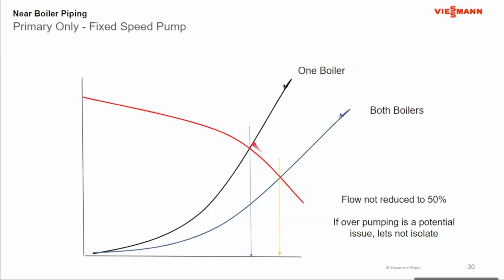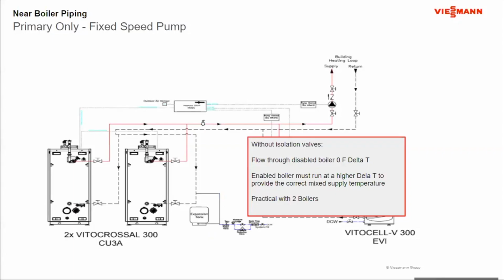And at this 1 boiler operating point, I start to worry about exceeding the maximum flow rate of that boiler. So with that fixed speed pump, we end up with 2 boilers with no isolation valves. If this boiler is firing and this boiler is not, I still see flow through both of them. The off-service boiler basically becomes a bypass. Return water comes in, flows through the boiler, picks up no heat, and continues out.